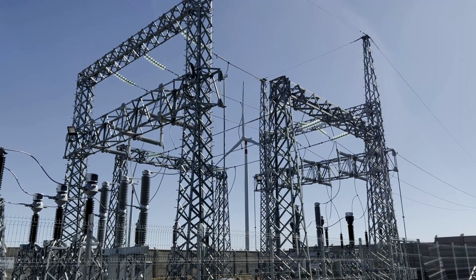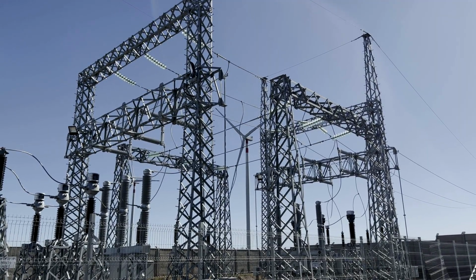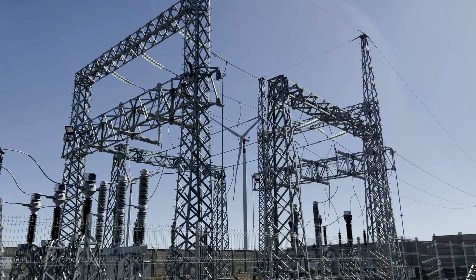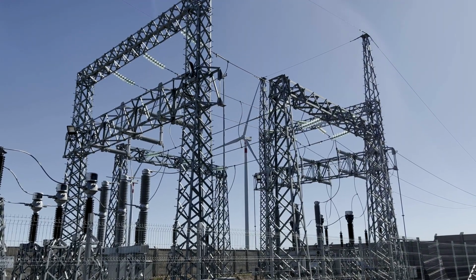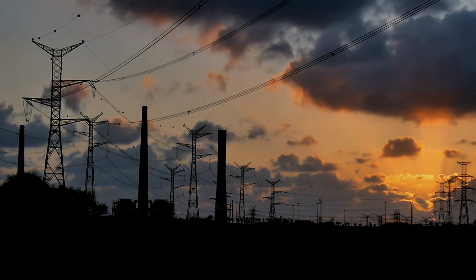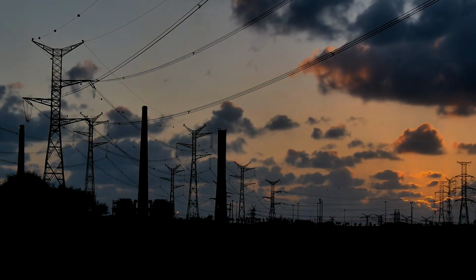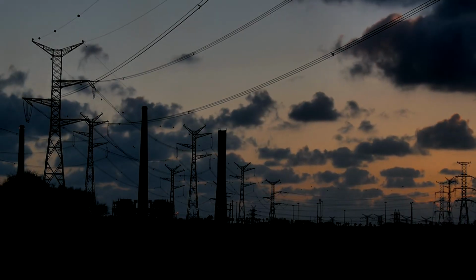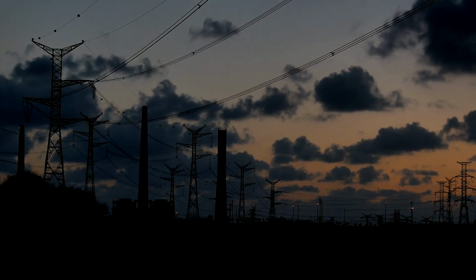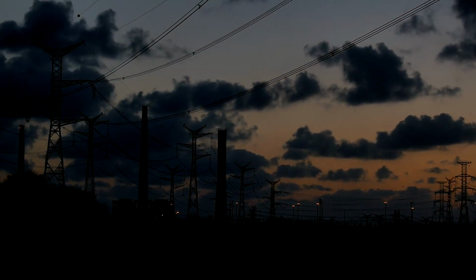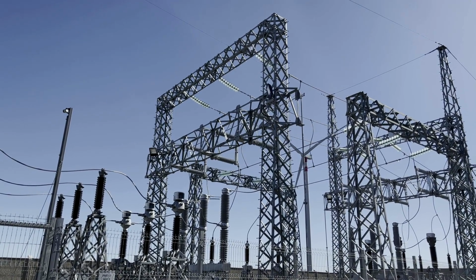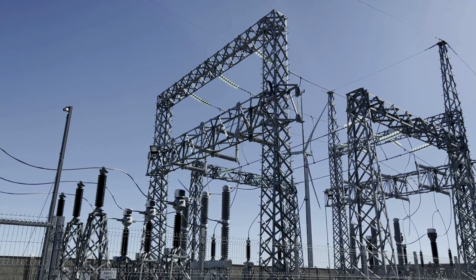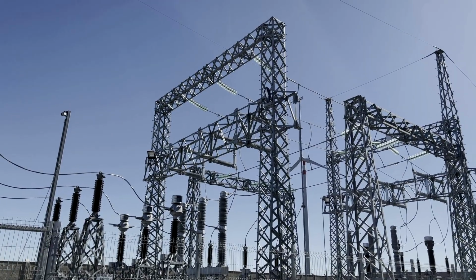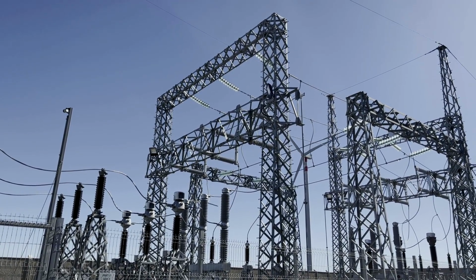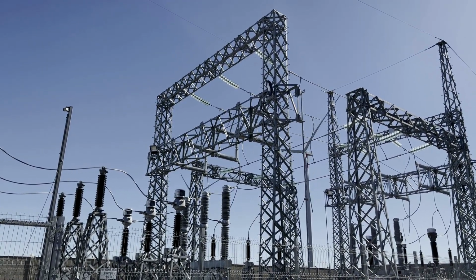It's the bulk movement of high voltage power between generating stations and the distribution networks that then fan it out to customers. Pivnichna, the substation Industroyer hit in 2016, operated at 330 kilovolts, a transmission class voltage, not a distribution one. A transmission substation typically feeds multiple distribution networks downstream of it.